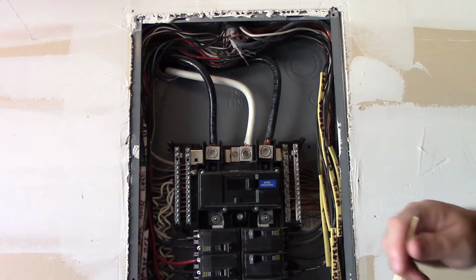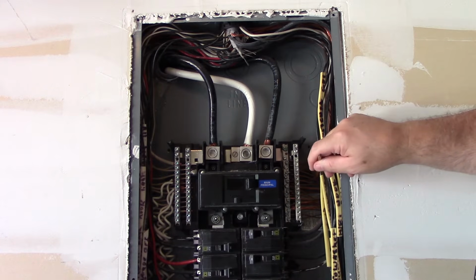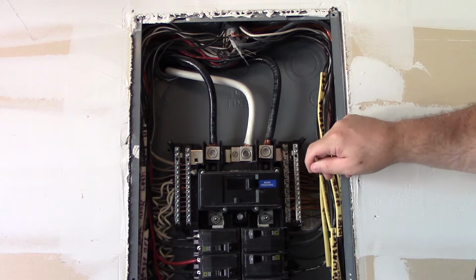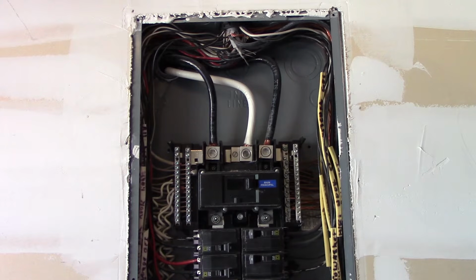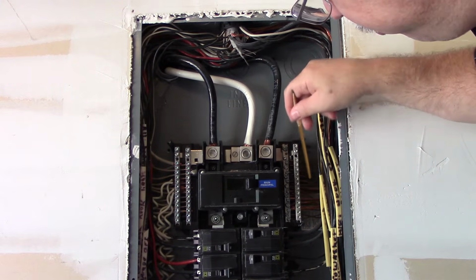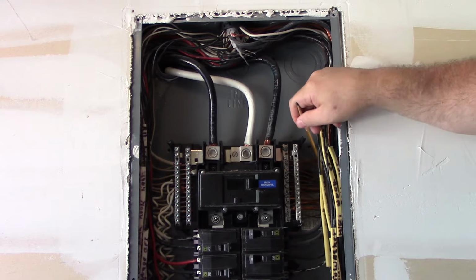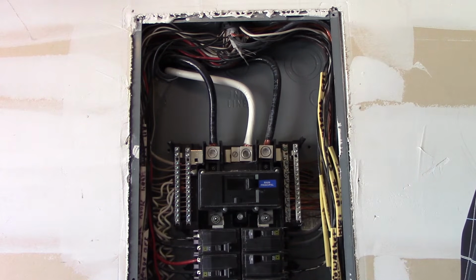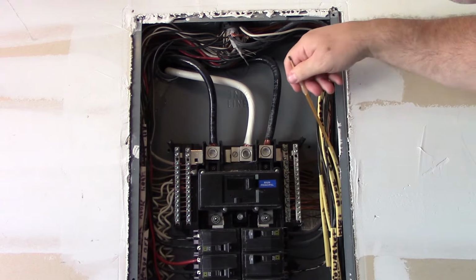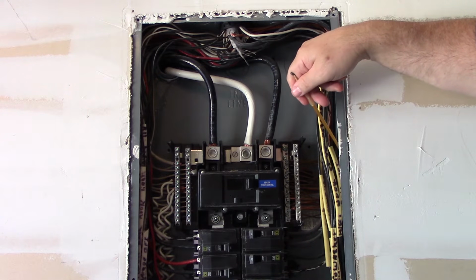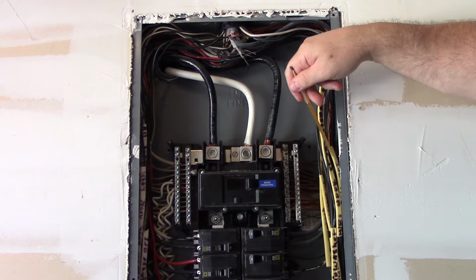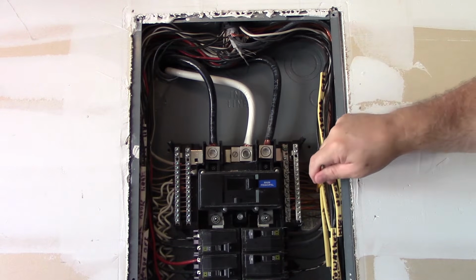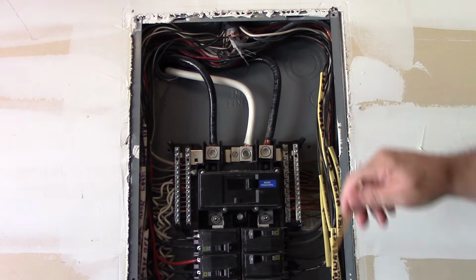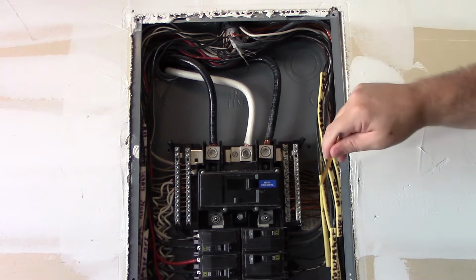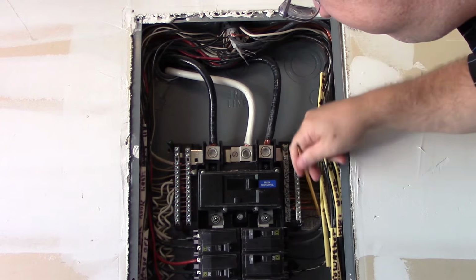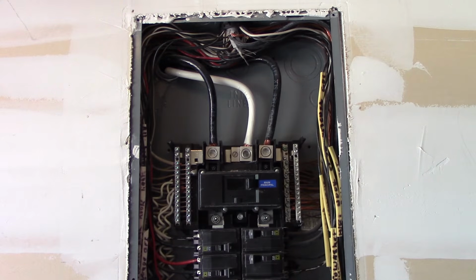The next thing I would have to do is install a totally separate equipment grounding terminal bar on this cabinet. And here you see there are screws under here that tell you where and how to install that equipment grounding terminal bar inside of here. And this label over here is going to tell us, and we'll see this later, the model number when we have to order the bar that goes inside of this actual cabinet. Okay, so that information is going to be found here, and we mount it right over here, and there are actually threaded screws here for mounting that bar in here.